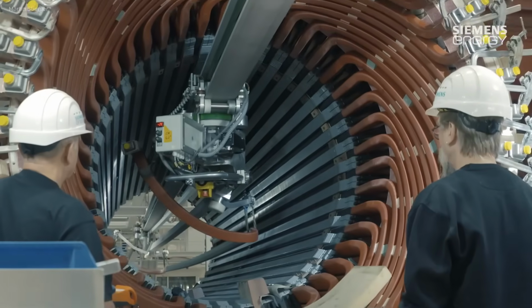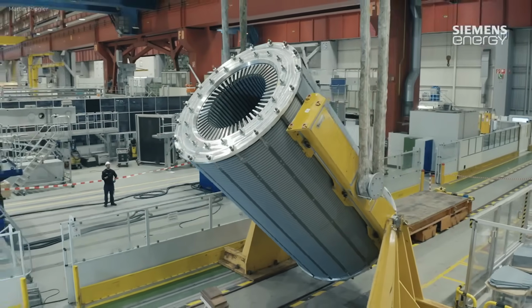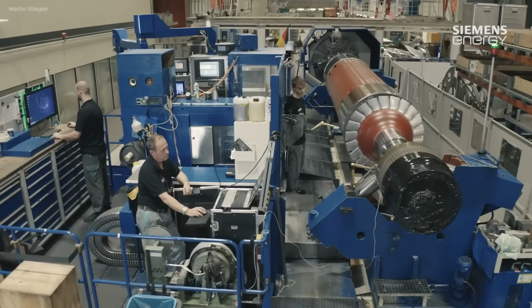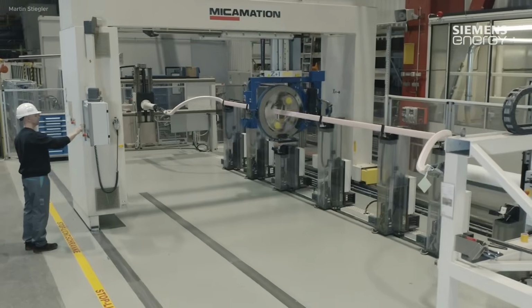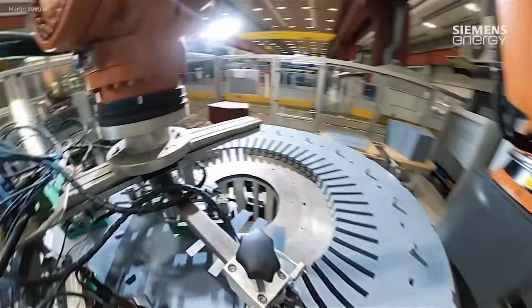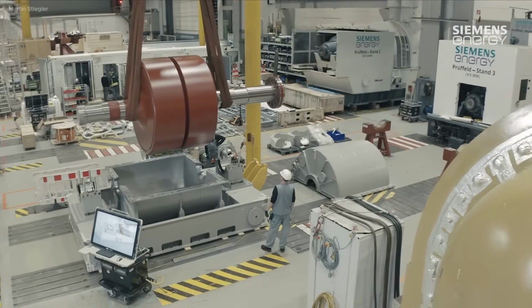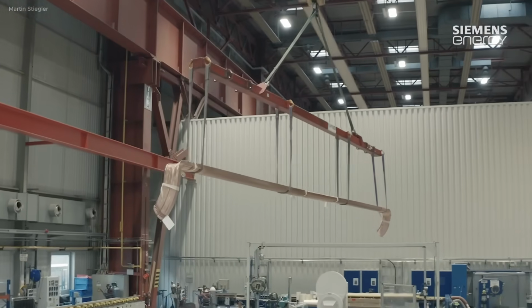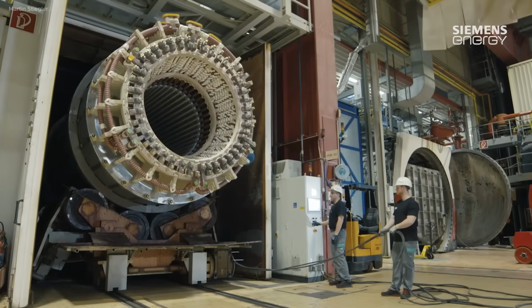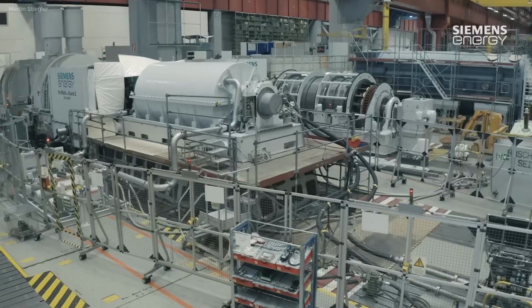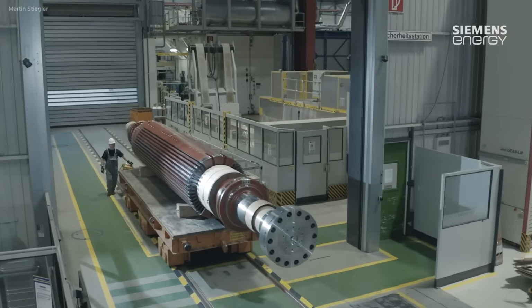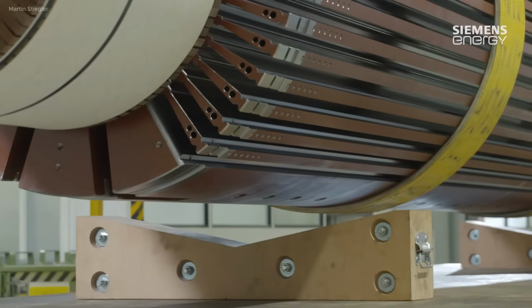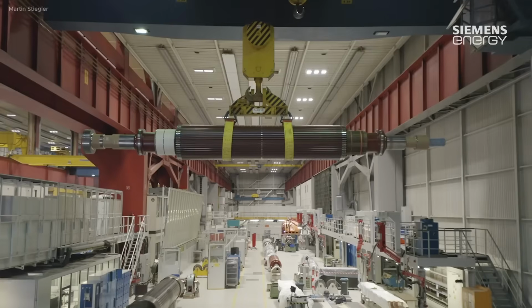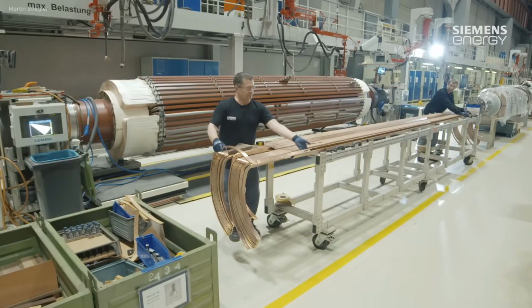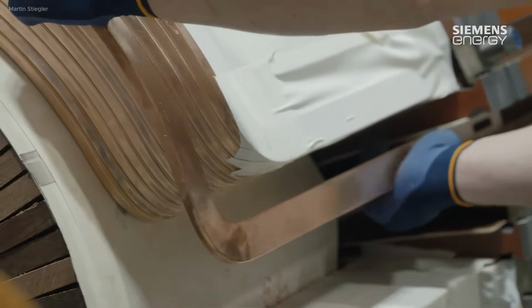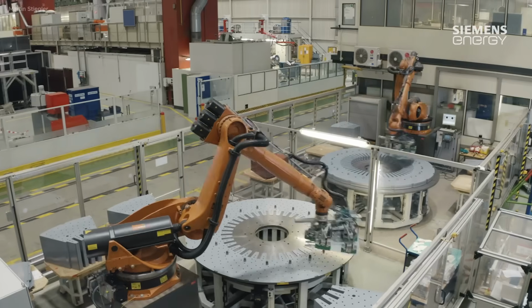The production begins with the stator, where conductors are inserted and soldered into place using ergonomic winding stations. Solder joints are ultrasonically tested, and the stator is assembled further. Meanwhile, the stator core is created by stacking over 100,000 steel laminations into a large welded package. It is then rotated horizontally for bar insertion. After bar positioning and insulation, the assembly undergoes vacuum resin impregnation to eliminate air pockets and ensure durability.